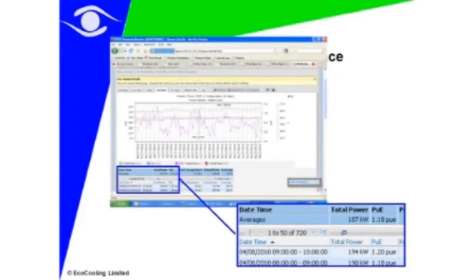M247 is a well-managed business. Many data centres don't really measure themselves at all, and some measure themselves in a very crude way. M247 looks at itself every 30 seconds and knows what's going on. They're monitoring their PUE temperatures continuously and calculating their PUE continuously. After this was installed, we were getting a PUE of 1.2, 1.18 — I think the lowest I've seen there is 1.17.